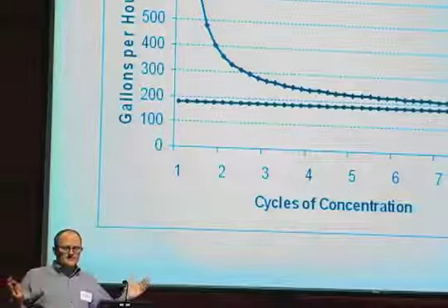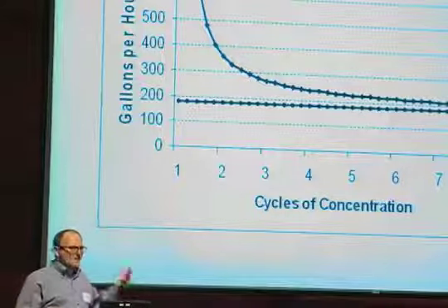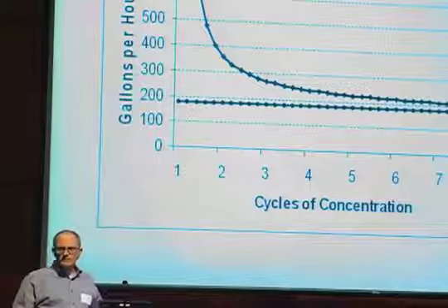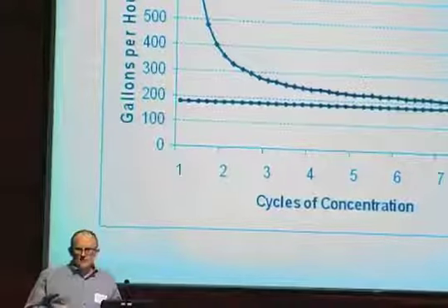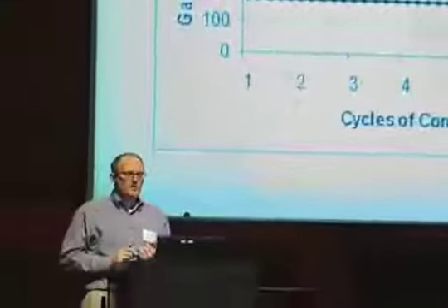So the big sense is if you can reduce your heat load, obviously you can significantly reduce water use in your system. And so, you know, you could be talking about things like the efficiency of the chillers that we were talking about previously in the question and answer session, or you could be looking at more efficient lighting, lower lighting levels, better glazing, all these sort of things that we don't normally think of as water savings opportunities are basically available in there if you can reduce load. So energy conservation really is water conservation. And in a lot of sense, since it takes water, takes energy to deliver water and to treat water, water conservation is energy conservation. So it's important to kind of look at that in the big picture.